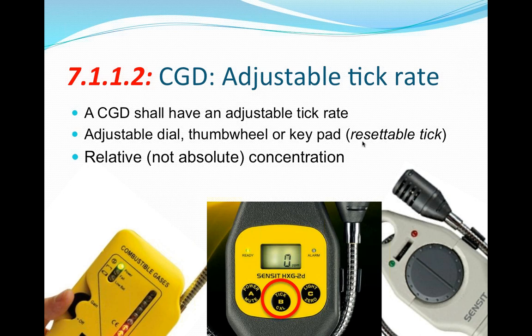And basically, the requirement is they're looking for a relative indication, not an absolute indication of concentration. However, if you went for the gold here and got something with a digital display like the Sensit HXG2D, that's fine, as long as it has some way of determining the volume concentration in a relative sense. So you're looking for more here and less there. That's what you're trying to find out when you're using a leak detector in this kind of mode.